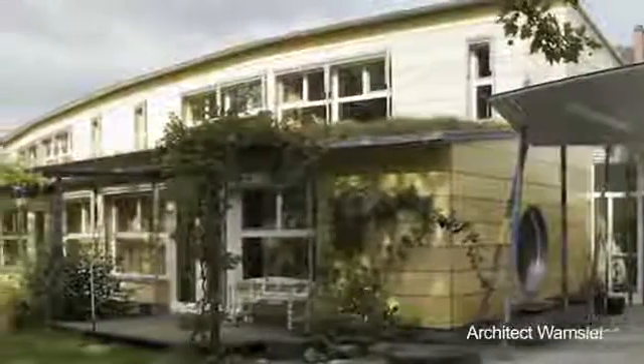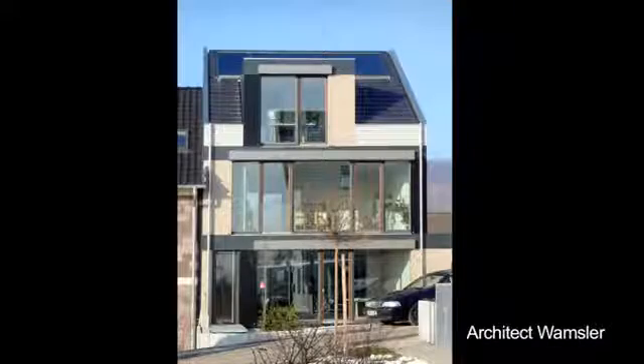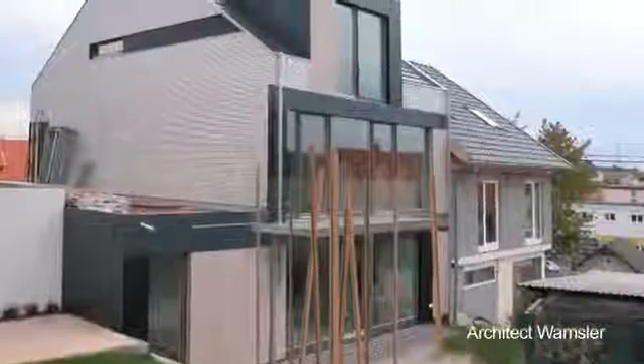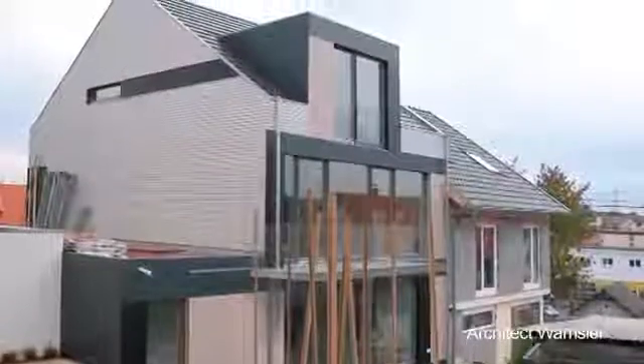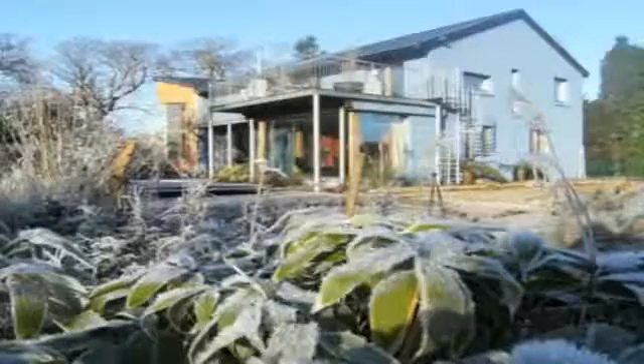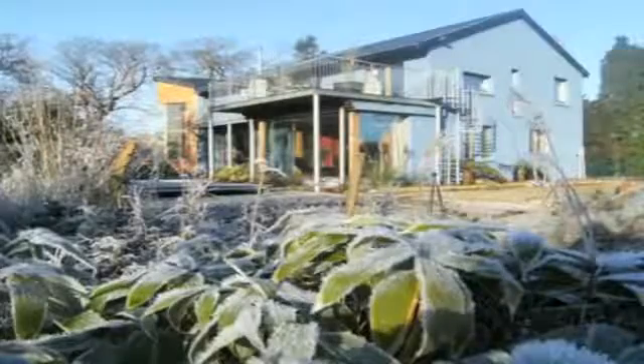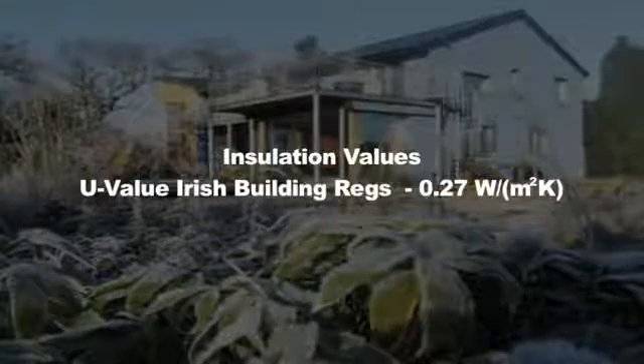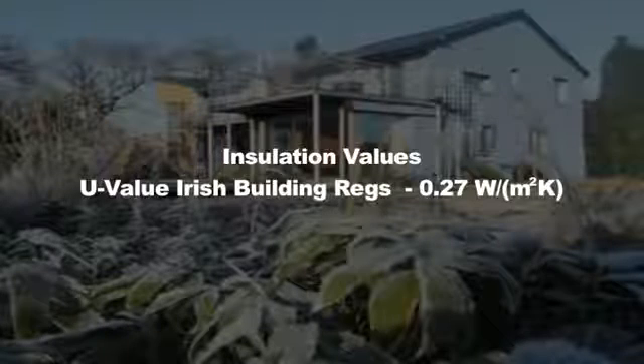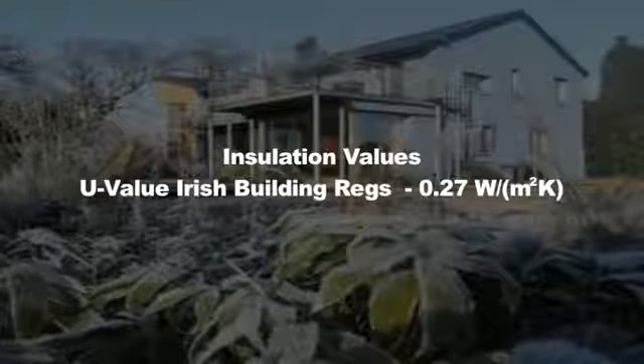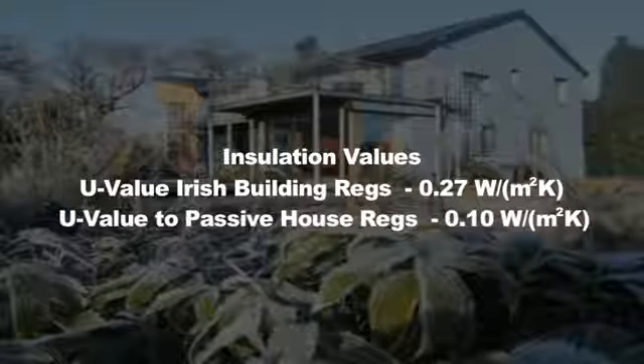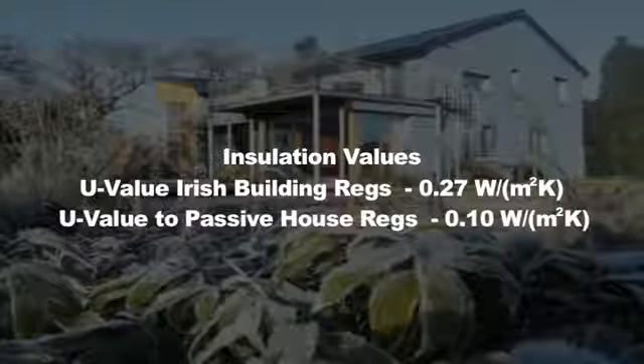Now, you have to remember the Passive House standard was defined 20 years ago, that's 2 decades ago. And the standards that were defined back then for Passive House in terms of insulation and airtightness still greatly exceed current building norms. So to give you an example, the current U value required by Irish building regulations is around 0.27 watts per metre Kelvin, whereas we'll be seeing in this series walls which have a U value of 0.10. That's 2.5 times better insulation standard.